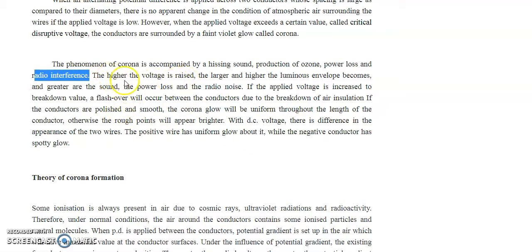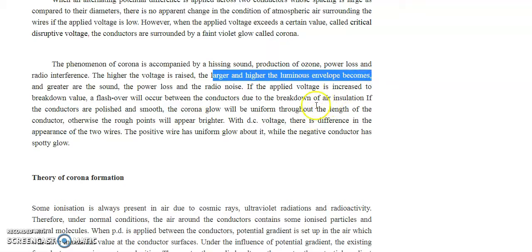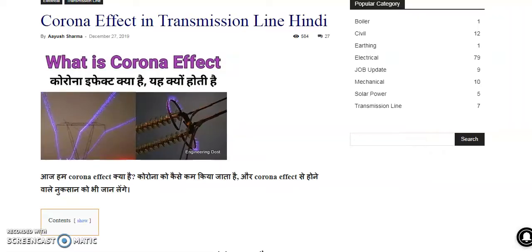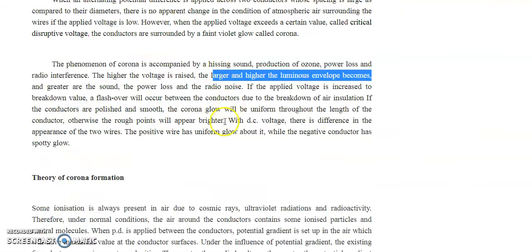The higher the voltage rise, if you increase the voltage to a higher magnitude, the larger the illumination envelope becomes, right? For example, I will show you an image of corona. Here you can see the transmission line. The transmission line itself is surrounded by a faint violet glow, and the jumper conductors, everything will be glowing. And if the air medium has high moisture, this glow will be very bright. Now we are going to discuss this corona effect, right? Yes, this one, corona effect.